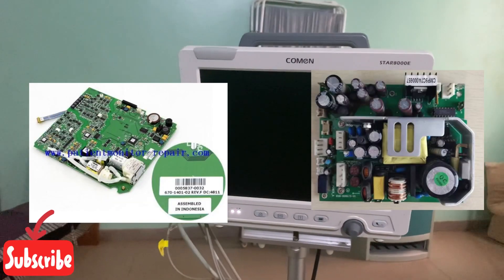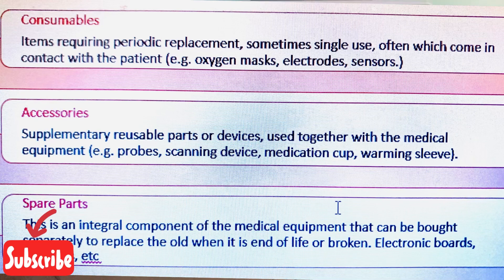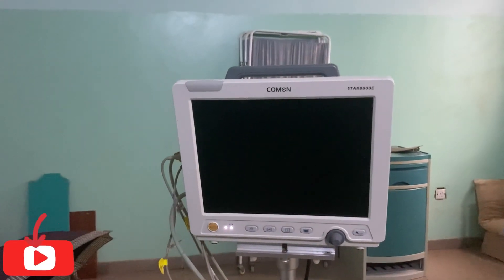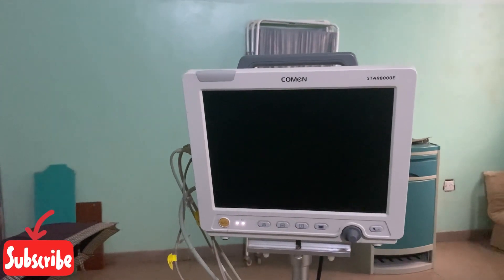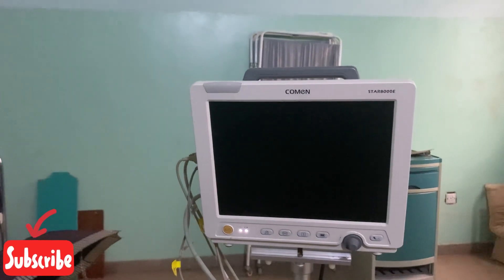To recap: accessories are items used frequently on different patients; consumables are discarded after every use; and spare parts are part of the machine which carry out a function or aid the functionality of the machine. That's all about the difference between consumables, spare parts, and accessories for a multi-parameter patient monitor. Thank you for watching — don't forget to like, share, and subscribe if this is your first time on this YouTube channel.